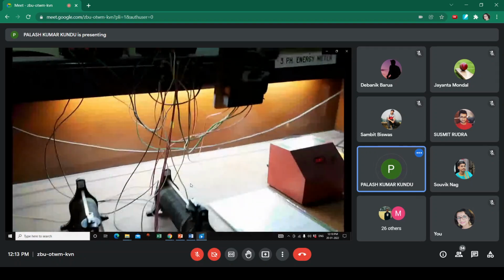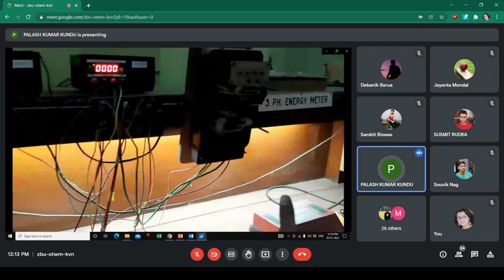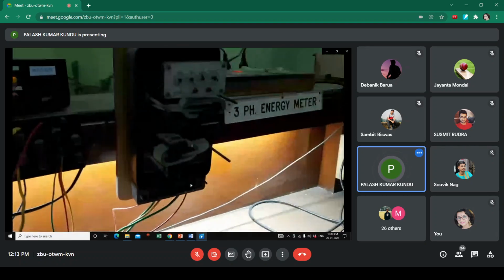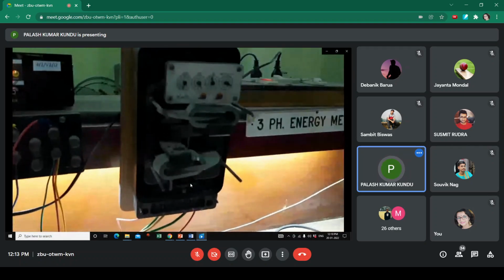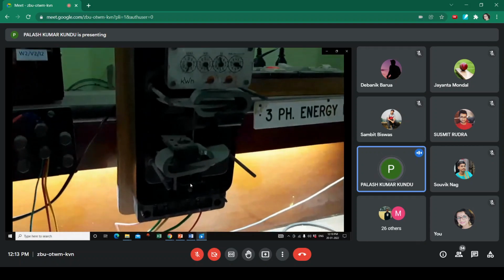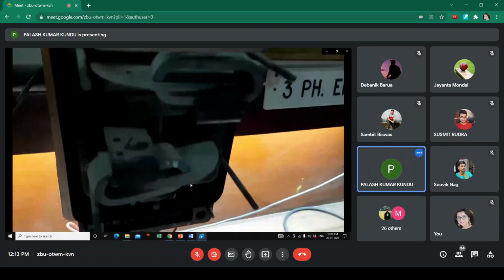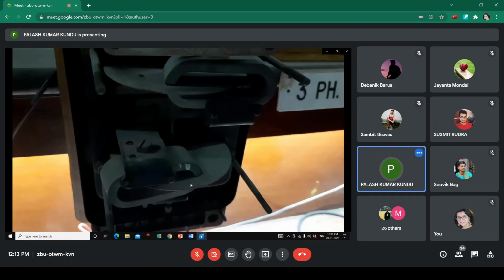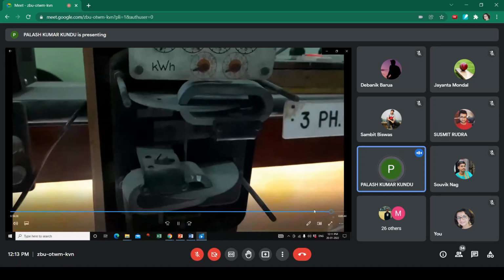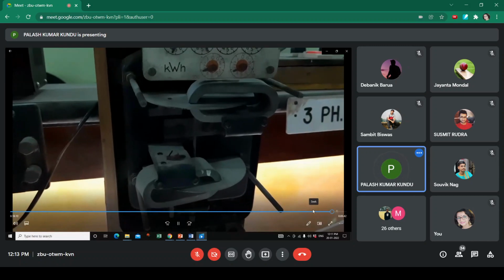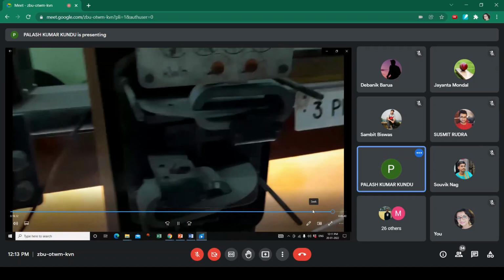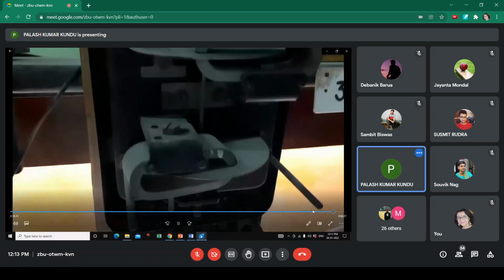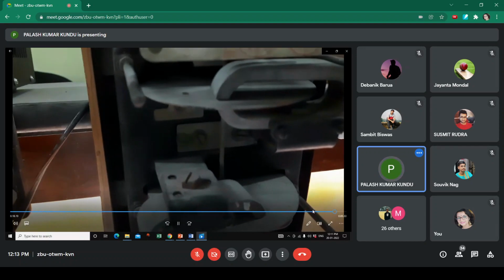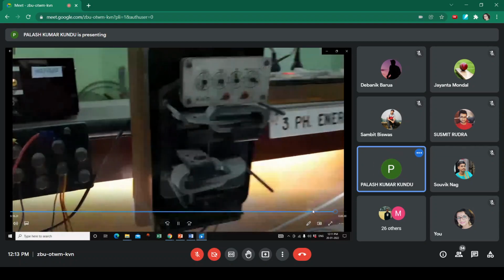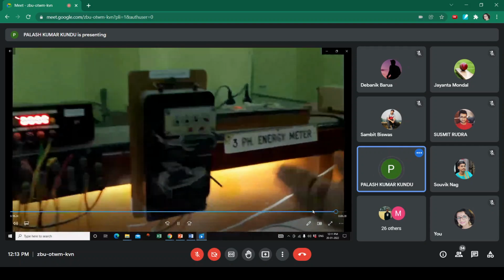you can see we already de-energized the current coil. So in that condition, the potential coils are energized only. In that condition, if the disc rotates, we can say in the meter there is creep. But if the disc does not rotate, then there is no creep in this meter. Disc is not rotating, both the discs are not rotating. So you can say that there is no creep at all.